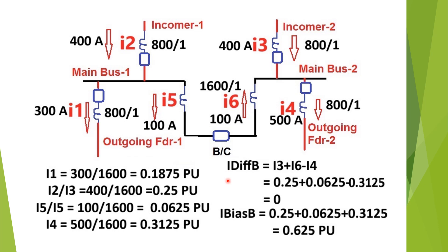Similarly, for zone B, i_diff_B = i3 + i5 − i4 = 0.25 + 0.0625 − 0.3125 = 0. The differential current for zone B is again zero in per-unit value. The bias current for zone B = i3 + i4 + i5 = 0.25 + 0.0625 + 0.3125 = 0.625 pu.